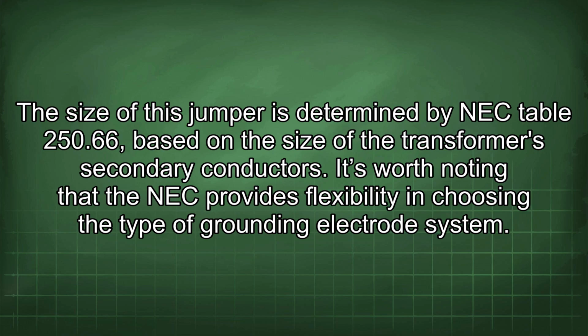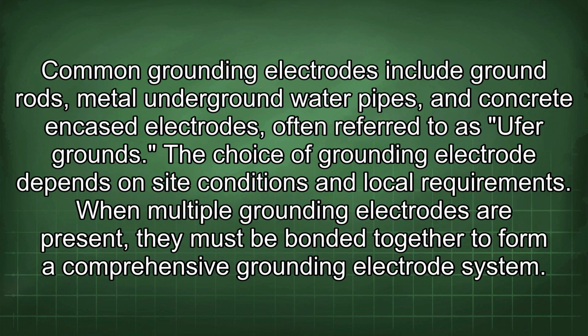It's worth noting that the NEC provides flexibility in choosing the type of grounding electrode system. Common grounding electrodes include ground rods, metal underground water pipes, and concrete encased electrodes, often referred to as Ufer grounds. The choice of grounding electrode depends on site conditions and local requirements.